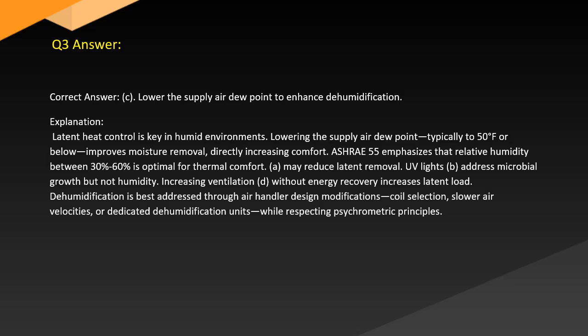UV light, B, addresses microbial growth but not humidity. Increasing ventilation, D, without energy recovery increases latent load. Dehumidification is best addressed through air handler design modifications: coil selection, slower air velocities, or dedicated dehumidification units, while respecting psychrometric principles.